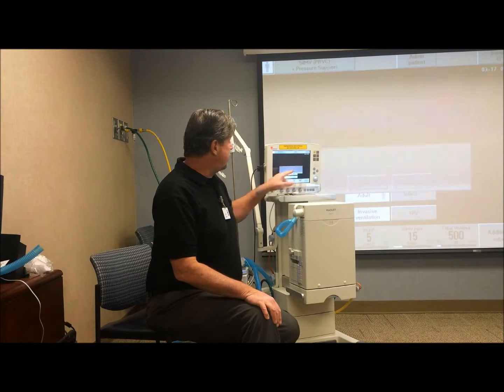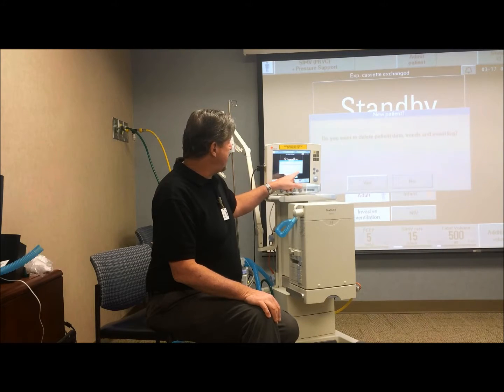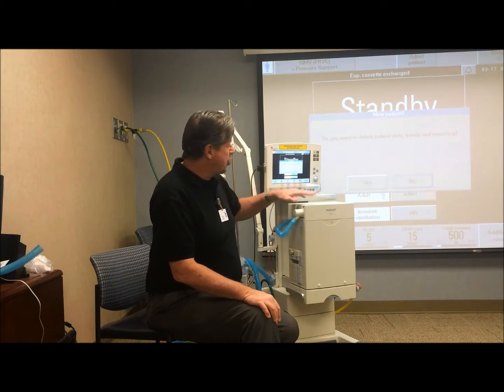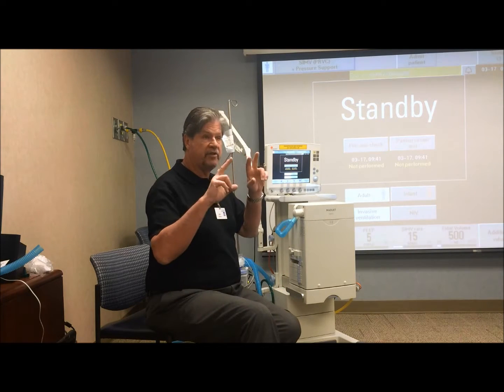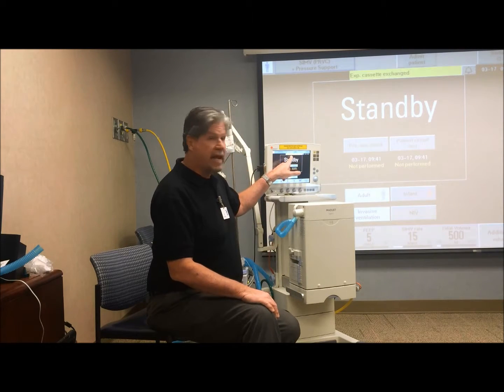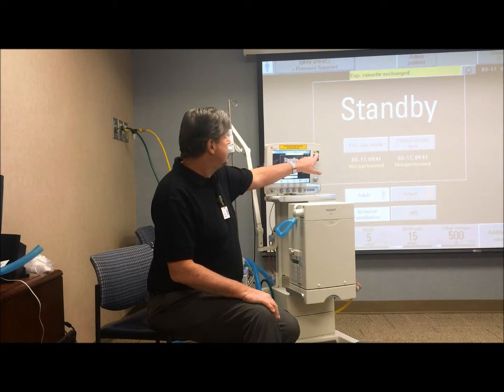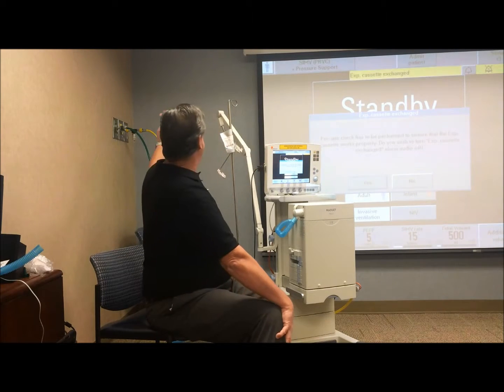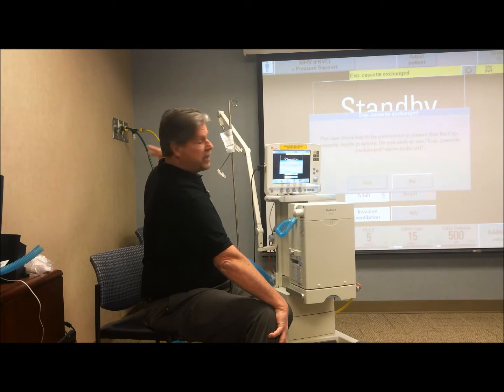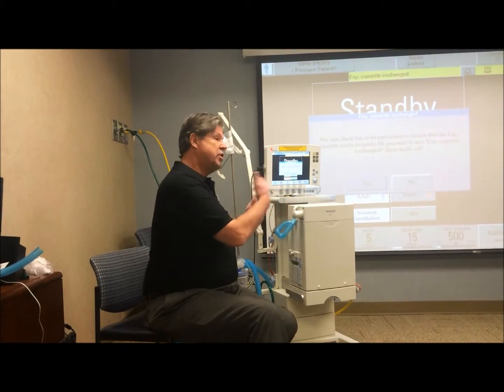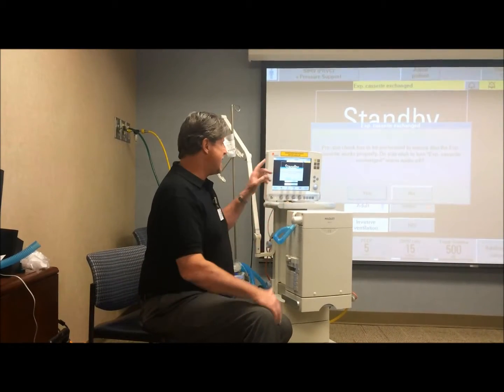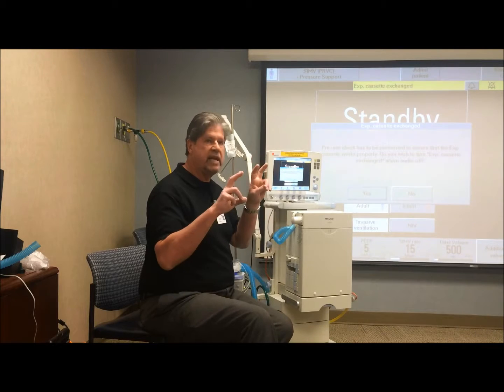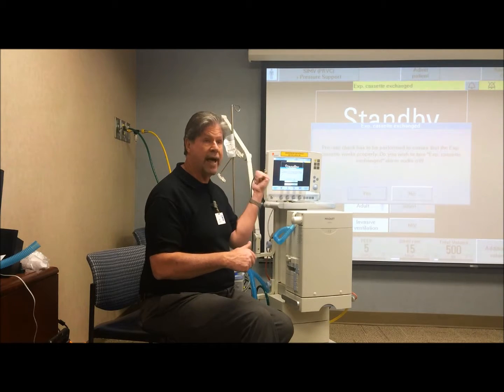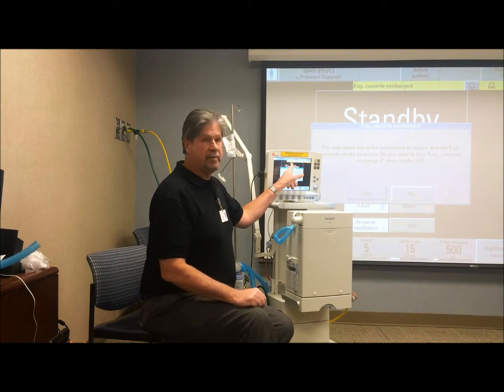Now, what happens is, and then you delete patient data, and now because we're using a cassette that hasn't been officially pre-use checked, we get this message. So because I don't have O2 and air, even if I put the ventilator through a pre-use check, it has to go through a complete official pre-use check with O2 and air to clear this message.